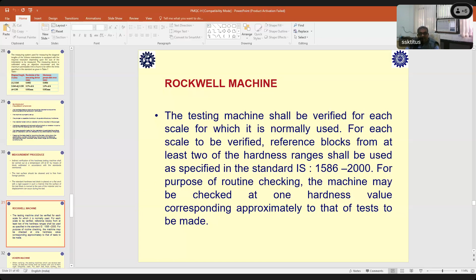Then next one is similarly for the Vickers. When verifying the testing machine which is used for several test forces, at least two forces shall be chosen, with one of them most frequently used. This is what I was mentioning in the previous one. Again, you see the word one of them, because normally all the scales are not very commonly used. I am repeatedly saying this because you have seen the complete spectrum of scales in the Rockwell, even the Vickers, from 0.01 gram to say 100 kg, and the original 1 kg to 3000 kg. You have seen the spectrum.